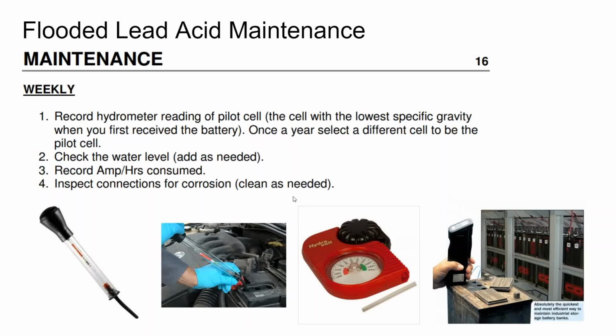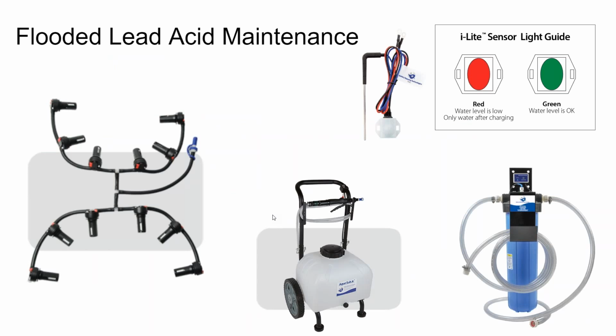The main thing you need to maintain on a battery bank is that when the battery is in use, it causes water to evaporate out of the battery. So there are plenty of watering systems, some which can even be automated and water your batteries automatically. But really, watering your battery is no big deal. In fact, it's less than a 2-minute process. It's literally just taking a watering tank and connecting it up to a nozzle that then fills all the batteries in your bank.